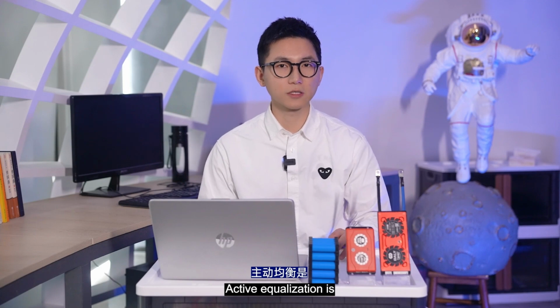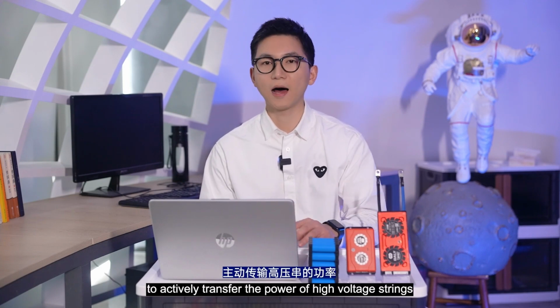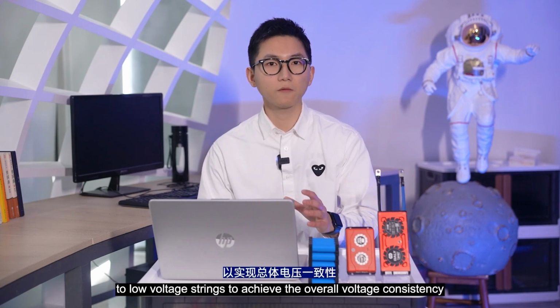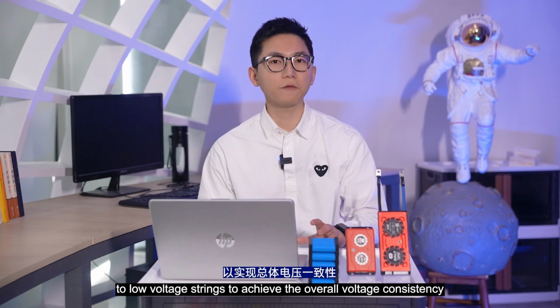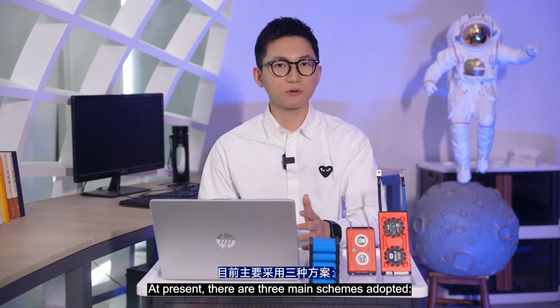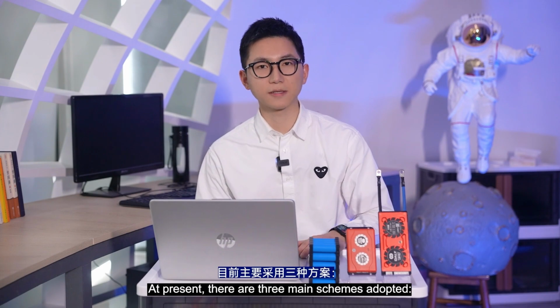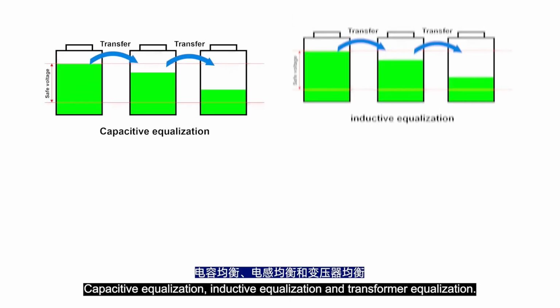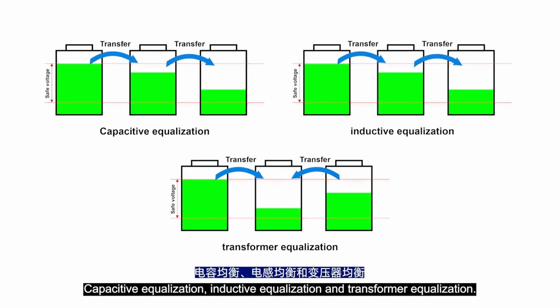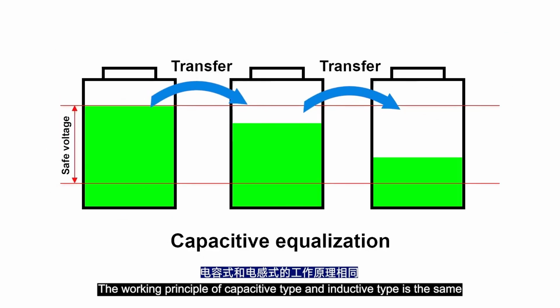Active equalization is to actively transfer the power of high voltage strings to low voltage strings to achieve overall voltage consistency. At present, there are three main ways adopted: capacitive equalization, inductive equalization, and transformer equalization. The working principle of the capacitive type and inductive type are the same.